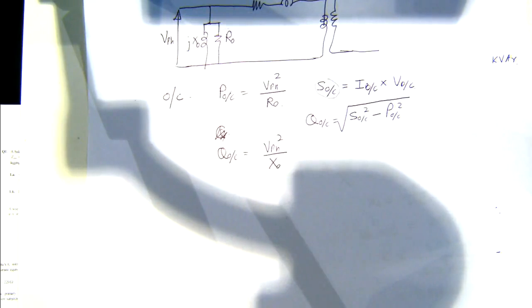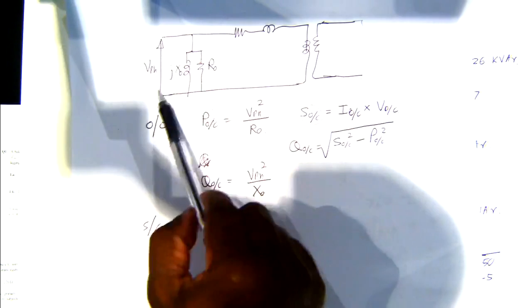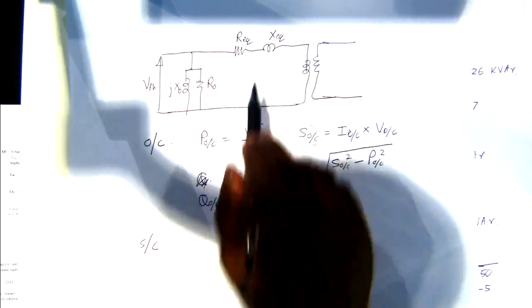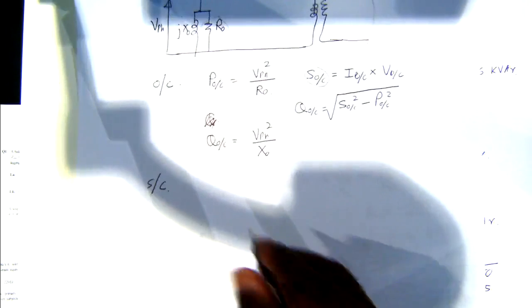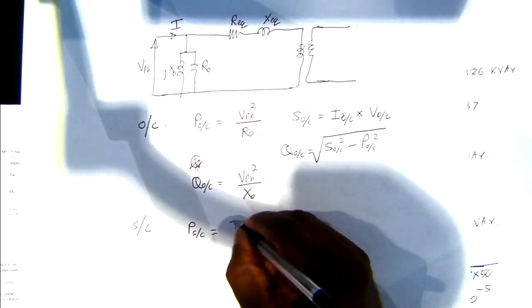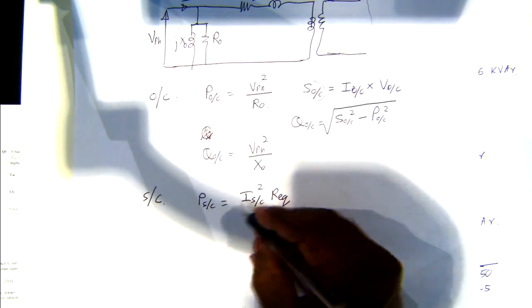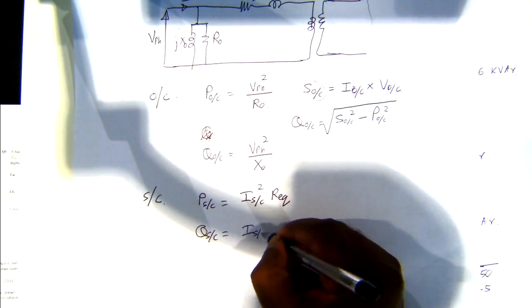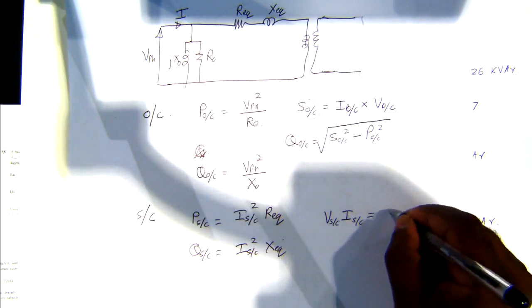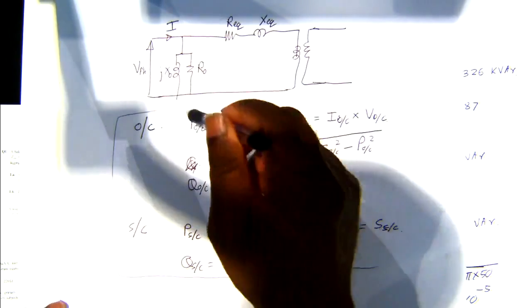For the short circuit test, we short-circuit the secondary. This results in high current, so we neglect the shunt circuit. P_SC equals I_SC squared times R_eq, which gives the real power measurement. Reactive power corresponds to I_SC squared times X_eq. And the applied voltage times short circuit current gives you the apparent power.